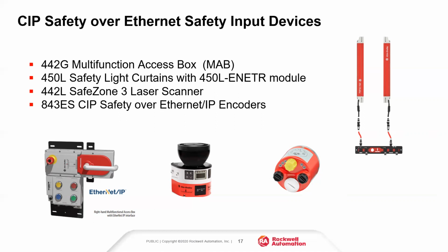The soon to be released, should be anytime this month actually, is the new 442L Safe Zone 3 laser scanner. This will be the first laser scanner on the market that has CIP safety built into it. It's configurable up to 8 zones, and has about a 5-meter sensing range in a very small package. Again, the whole idea is to have flexibility when you're setting up your system. Being able to configure 8 different zones via Ethernet and through an add-on profile in one program, versus having multiple programs for somebody else's safety scanner connected to your safety network, really decreases the startup time and troubleshooting time for your systems.